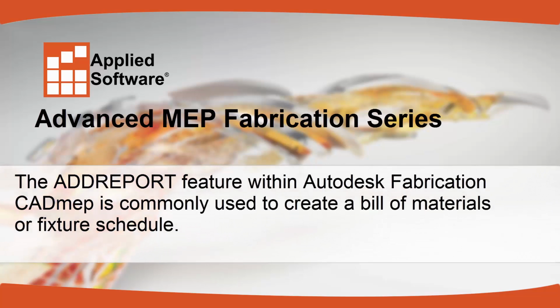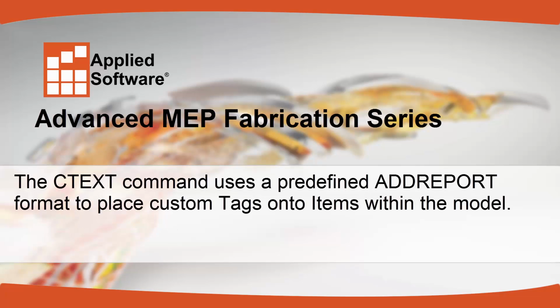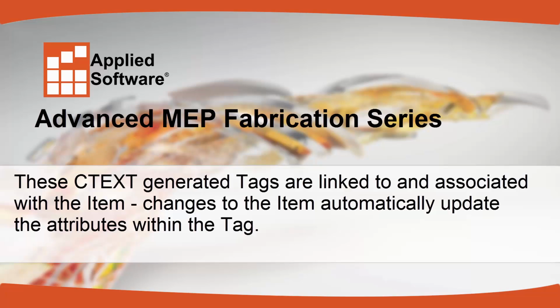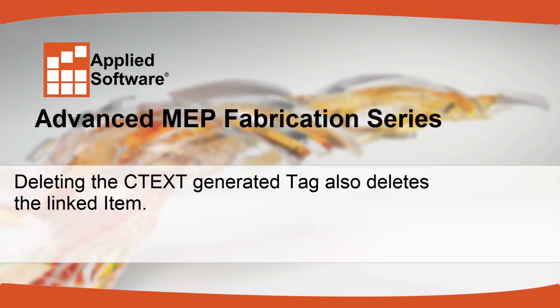The ADDREPORT feature within Autodesk Fabrication CADmep is commonly used to create a bill of materials or fixture schedule. The CTEXT command uses a predefined ADDREPORT format to place custom tags onto items within the model. These CTEXT generated tags are linked to and associated with the item. Changes to the item automatically update the attributes within the tag. Deleting the CTEXT generated tag also deletes the linked item.